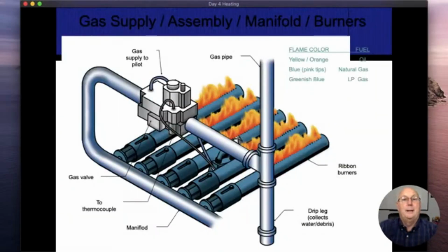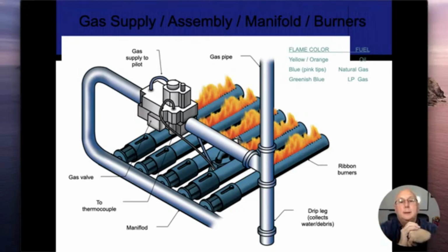All right, a little bit on the burners. I'm not going to go real heavy. Typical manifold burners on here. Those orifices that I was talking about, they're going to be at the bottom. My device actually went dead, so I can't put a cursor on there. Where the manifold comes in there's going to be a small pinhole. That's the orifice. If I change this from gas to propane, that orifice has to be changed out as well. Larger opening for gas, smaller opening for propane.